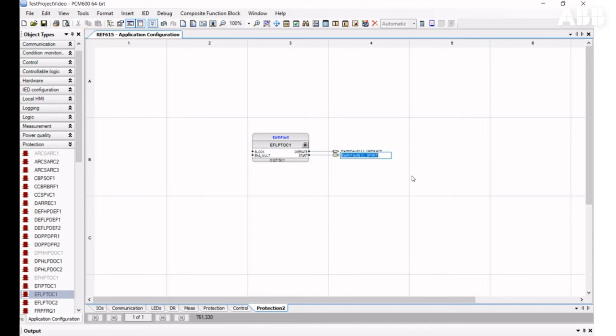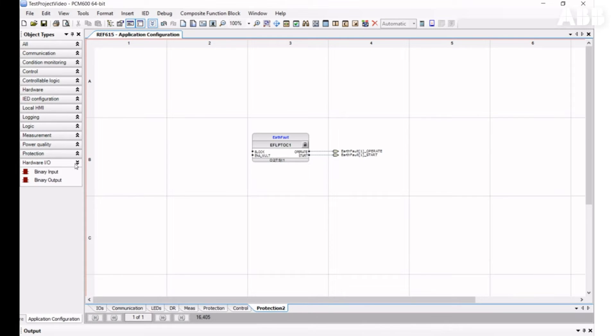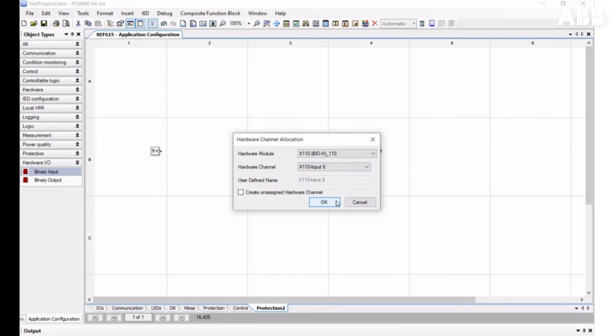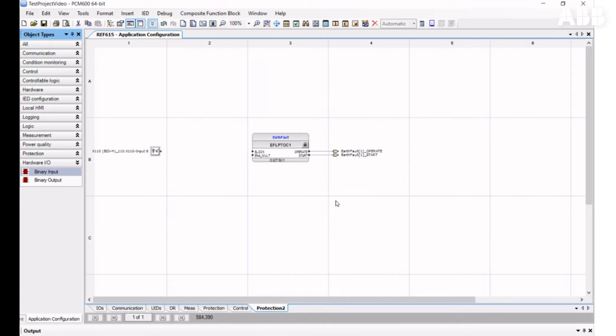Let's learn how to insert a binary input. You can take it from Object Types in the Hardware I/O category and drag and drop the binary input element. When it has been inserted, you need to choose the hardware module and hardware channel. Every relay has a different number of binary inputs divided into different modules. To select the correct one, you need to know the purpose of the binary input, which you can learn from the connection diagram or project specification.